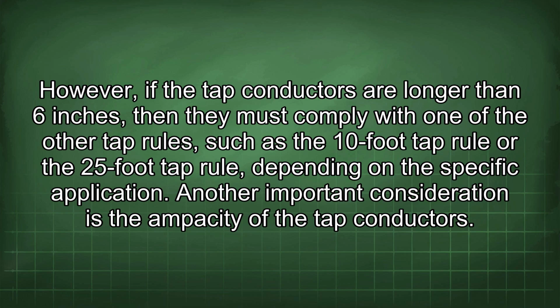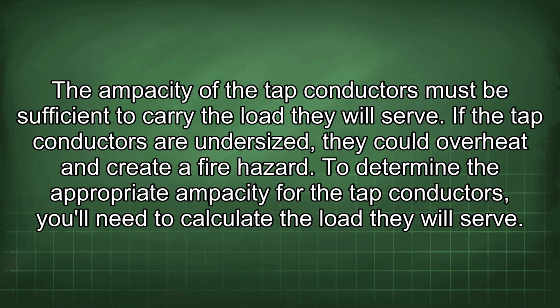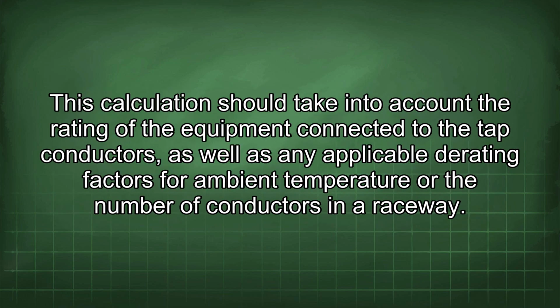Another important consideration is the ampacity of the tap conductors. The ampacity of the tap conductors must be sufficient to carry the load they will serve. If the tap conductors are undersized, they could overheat and create a fire hazard. To determine the appropriate ampacity for the tap conductors, you'll need to calculate the load they will serve. This calculation should take into account the rating of the equipment connected to the tap conductors, as well as any applicable derating factors for ambient temperature or the number of conductors in a raceway.